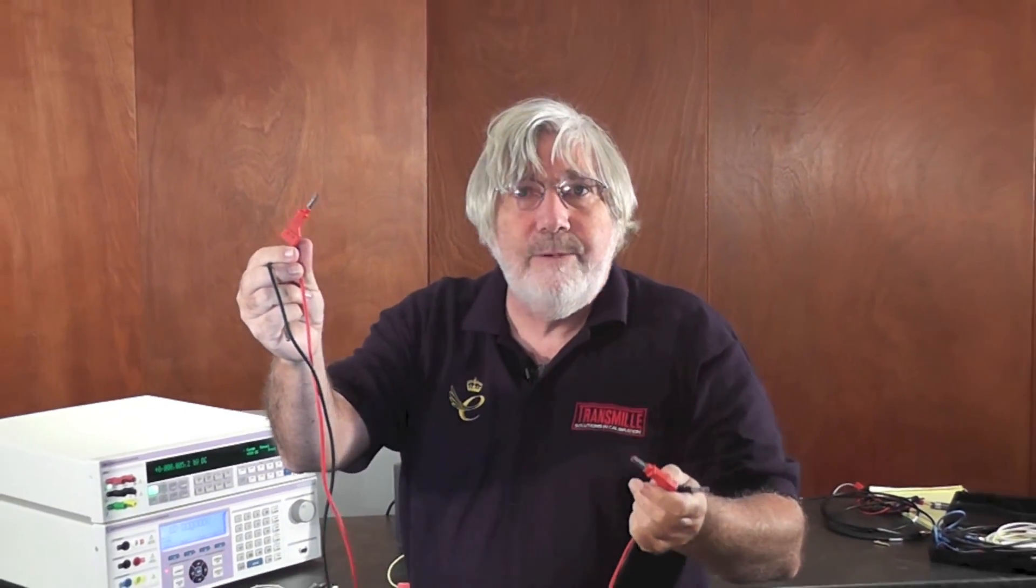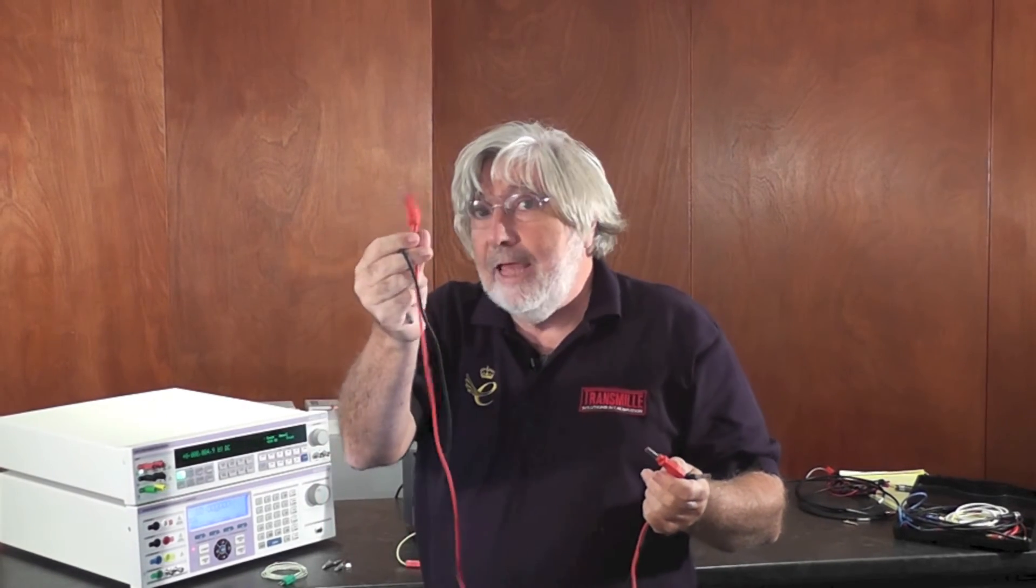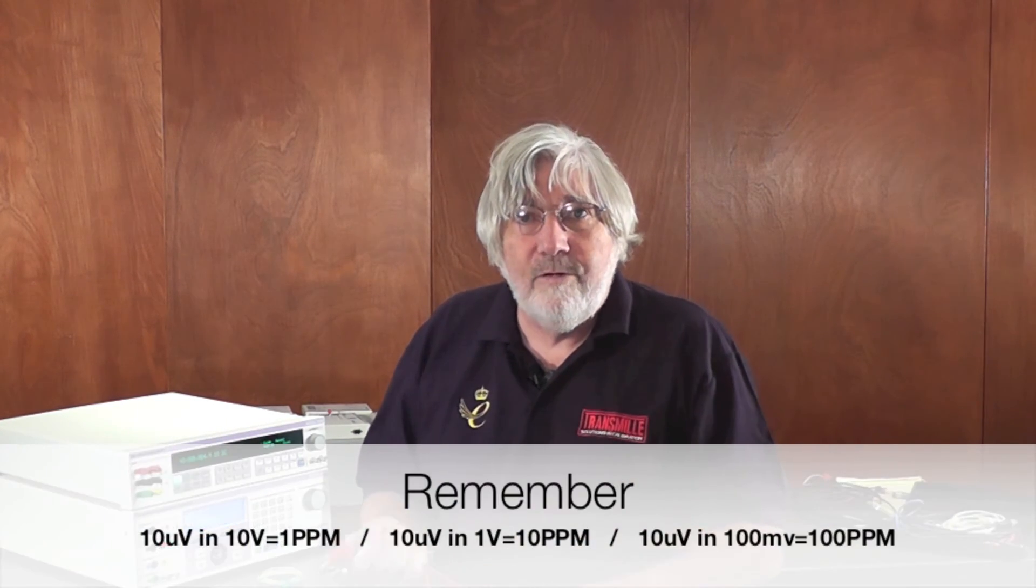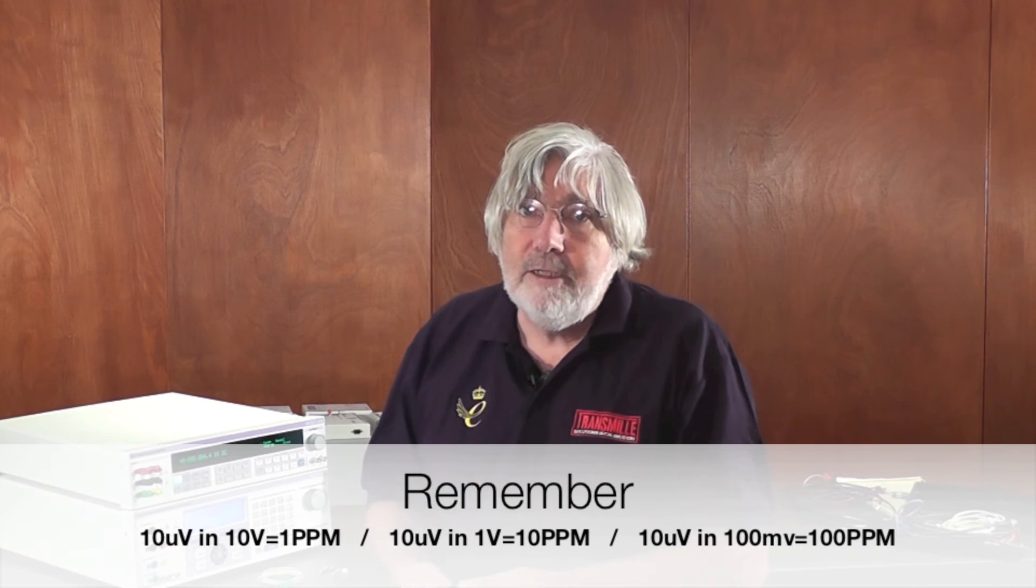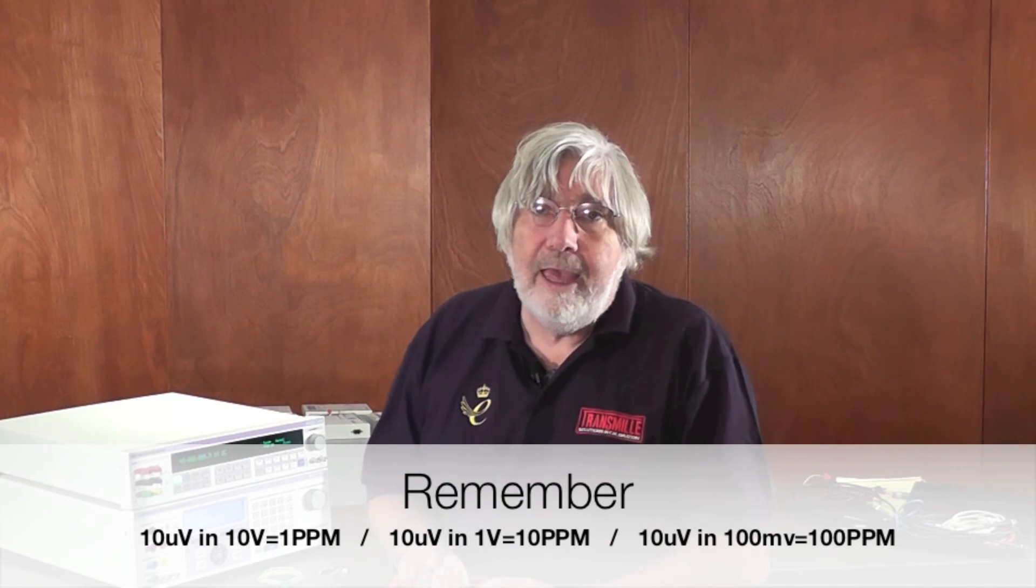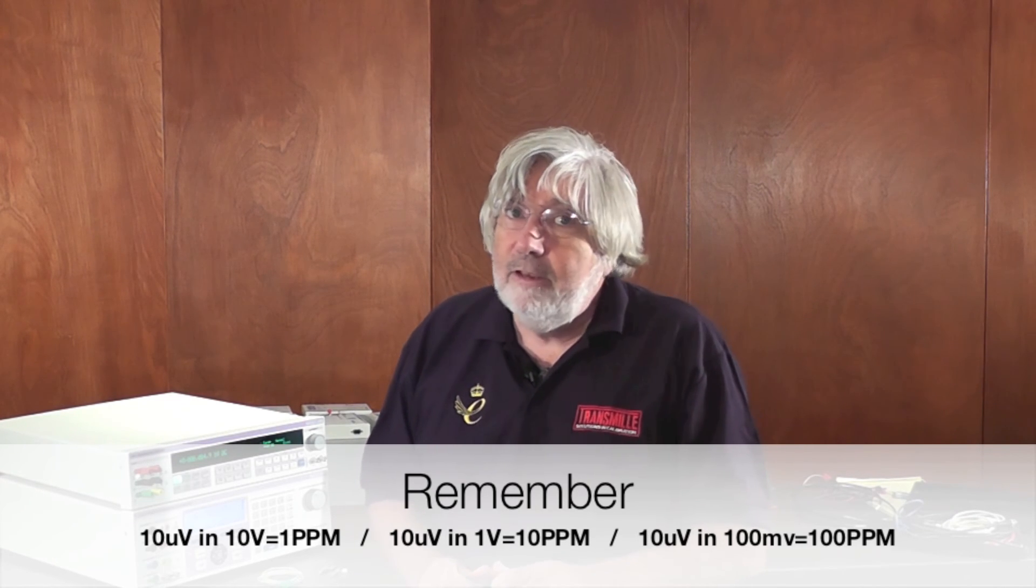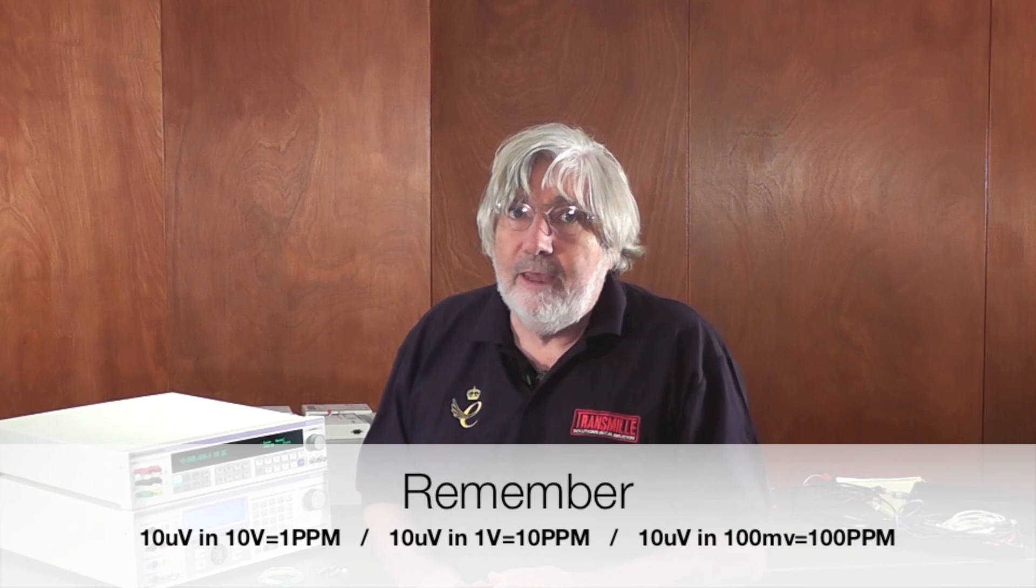Whereas of course the humble test lead that you'll probably pick up from your bench will be some kind of nickel or maybe if you're lucky silver plated brass, because obviously that is much cheaper and more hard wearing than the softer copper gold plated coppers used on the instruments. It's important that they should match. When you get dissimilar metals together you get high thermal voltages which will lead to errors of many tens of ppm when working at the one volt level, and when you're working at 100 millivolts level you're talking hundreds of ppm of error.